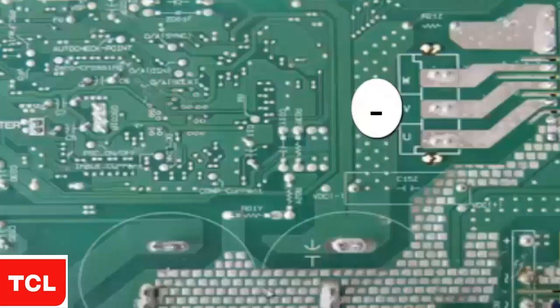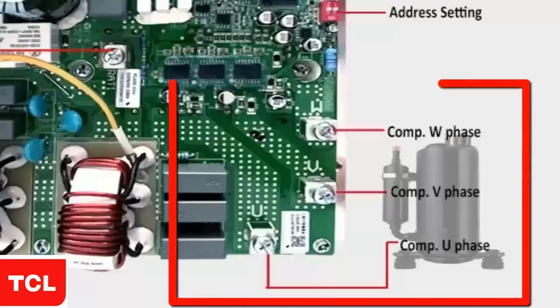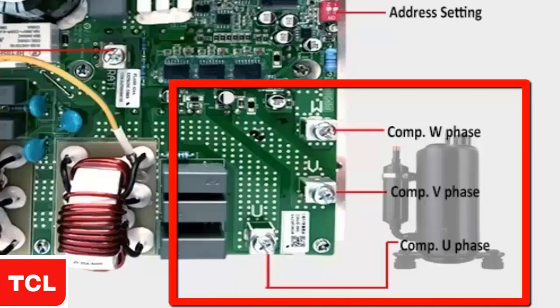Identify the output points UVW. These can be identified by following the tracks from the compressor connectors to the IPM electronic circuit.